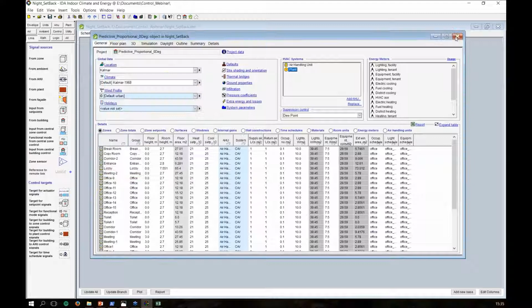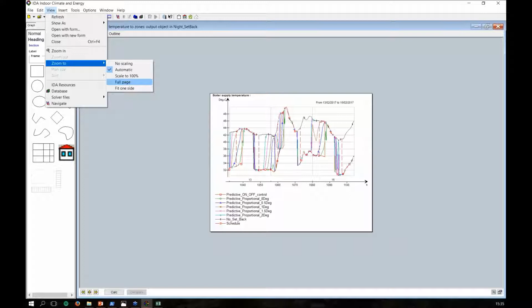I logged the boiler supply temperature to the zones. And this is the last thing I want to show you guys. So when we have no setback, the one that is blinking there on the screen is the temperature supply to the zones. And it's always high, around 42 to 48. When we have a scheduled setback, it cuts down at night from 4 in the morning to 5. You can see it here dropping down by 10 degrees to 32.